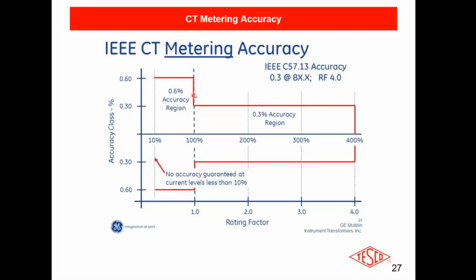So in a perfect world, if you think that you're going to typically have 200 to 300 amps on a particular customer's service, and yes, he may go up quite a bit at times when he's turning things on, and he may go down at times when there's nothing going on, you don't size a 200 to 300 amp load with a 400 to 5 with a thermal rating factor of 4. You really want to size that as maybe a 100 or a 200 to 5 with a thermal rating factor of 4. That would be a lot better for that size because your accuracy in here is actually less.